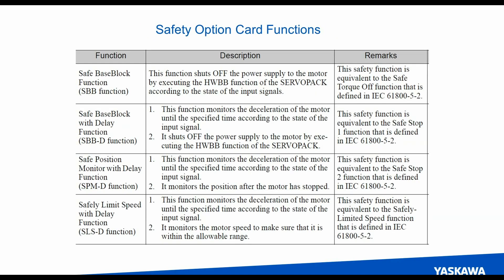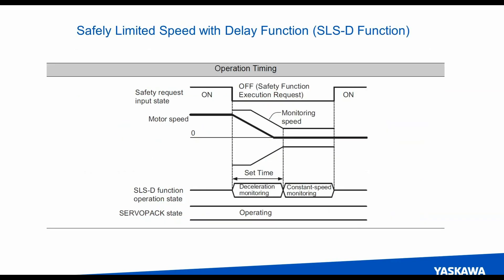These are the four levels or four versions of safety option card functionality that can be implemented. Today we're going to be focused on safe limited speed. If you're not familiar with safe limited speed, it's a functionality that when active monitors the motor speed and confirms that it's below a certain level. If the option card detects that the motor speed is above that level, it will then disable the axis. It does not have the power to slow down the motor by itself with a command. It's purely monitoring.